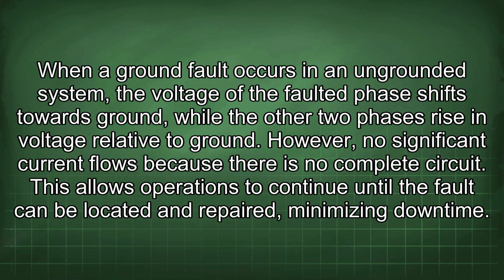When a ground fault occurs in an ungrounded system, the voltage of the faulted phase shifts towards ground, while the other two phases rise in voltage relative to ground. However, no significant current flows because there is no complete circuit. This allows operations to continue until the fault can be located and repaired, minimizing downtime.